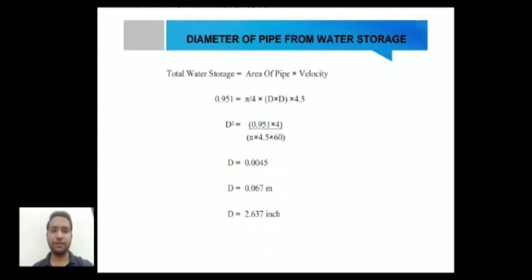Then we took reference from IS 15105 to select the sprinkler head. There are 5 sprinkler heads according to different discharges. So we have selected the 75 from the 150 lpm discharge sprinkler head. This is the calculation of the diameter of the water storage pipe. We applied the formula of total volume, which is area into velocity. Now 0.951 is the total water needed in cubic meters, then area, then velocity, which is the standard 4.5 meters per second. Now the diameter has come to 2.637 inch. In the next slide, we have calculated the distance between two sprinkler heads.